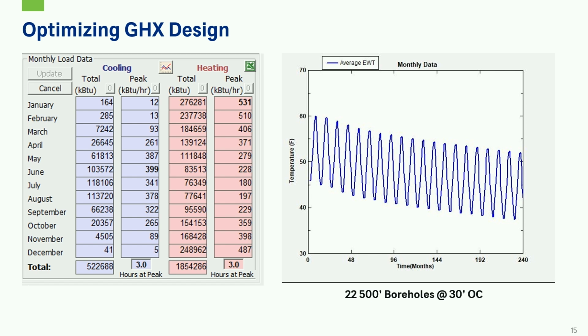So what we can do is really look at those annual loads because they dominate the thermal drift, but there are some small changes that we can make in the optimization of the ground heat exchanger to mitigate that drift. So if we look at this example, we have a residential building that's heating dominant, so we're seeing that thermal drift of the ground cooling off. And we can see that there was a peak of 399 kBTUs per hour for cooling, and then we had a higher peak of 531 kBTUs per hour in January.